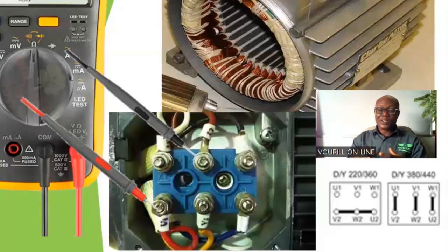So you test for the resistance of each of the windings. If you are testing the resistance of the U phase, you test between U1 and U2. V1 and V2 will give you the resistance of the V winding. W1 and W2 will give you the resistance of the W winding. Since the three-phase windings are exactly the same, expectedly you are supposed to have the same resistance in each of the windings, in milliohms, or in ohms, depending on the size of the motor. Smaller motors, you can have it in ohms.